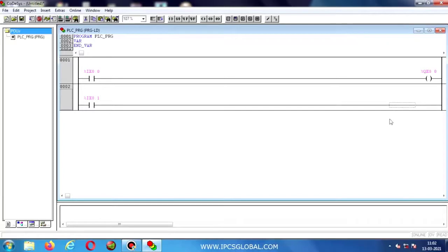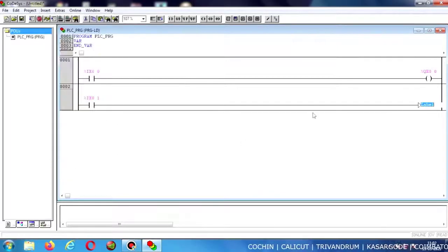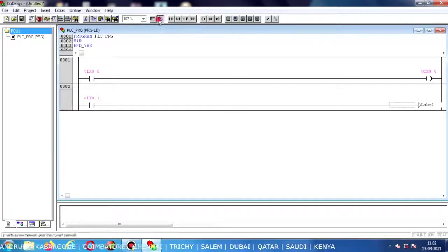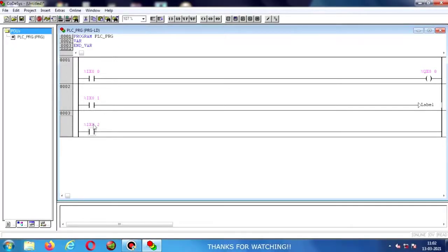Now I am creating a new network. In that also I am placing a new NO contact and giving another input address. Now I am going to use the Jump instruction — click the Insert option, in that the Jump instruction is available, click on it. The label command will be displayed and you should put any name for the jump command. Now I am creating a new network with input %I0.2 connecting with output coil %Q1.